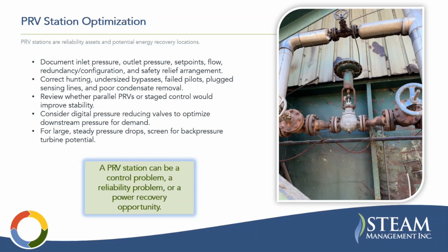That's a good efficiency scope. Basically, having a digital control valve control the downstream pressure based on the required demand. And then for large steady pressure drops, you want to screen for a back pressure turbine potential.